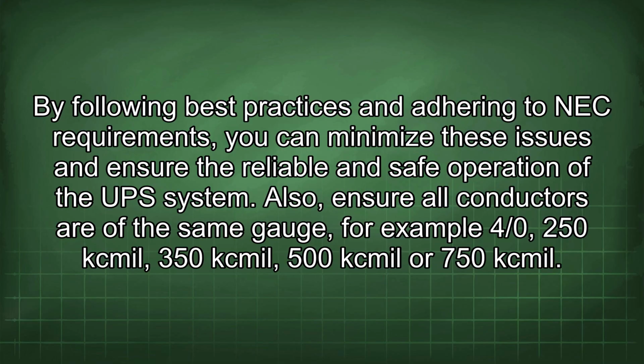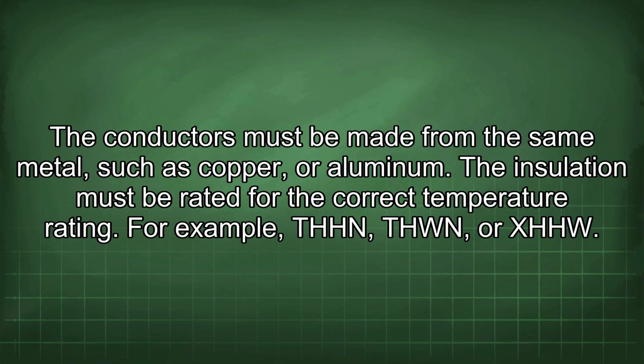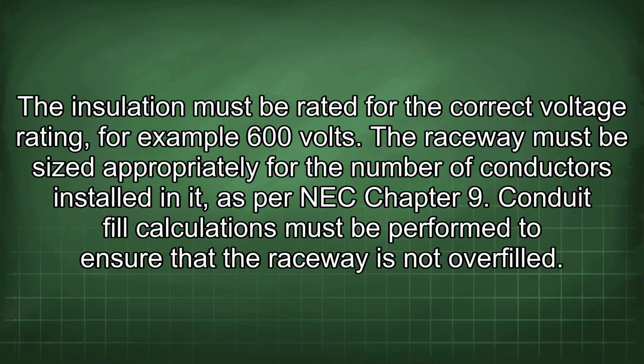Also, ensure all conductors are of the same gauge, for example 4/0, 250 kcmil, 350 kcmil, 500 kcmil or 750 kcmil. The conductors must be made from the same metal, such as copper or aluminum. The insulation must be rated for the correct temperature rating, for example THHN, THWN, or XHHW. The insulation must be rated for the correct voltage rating, for example 600 volts.